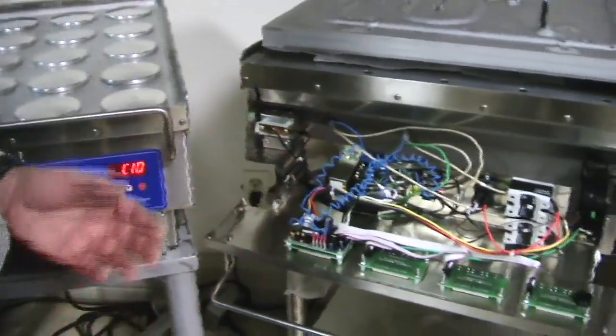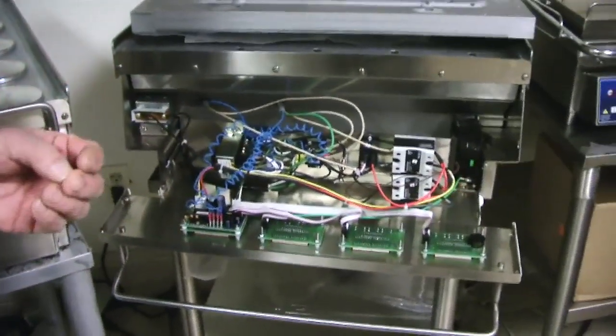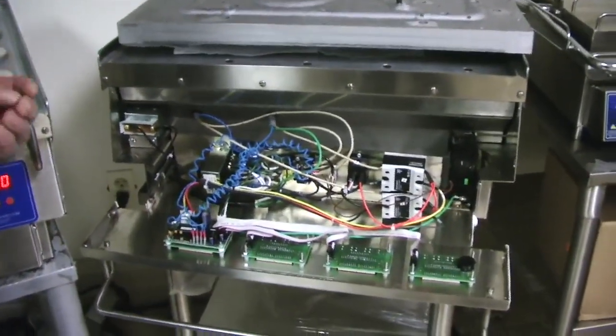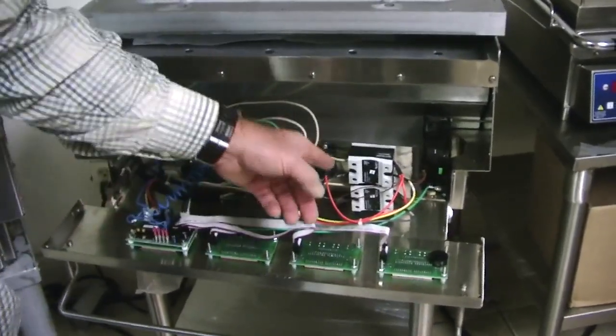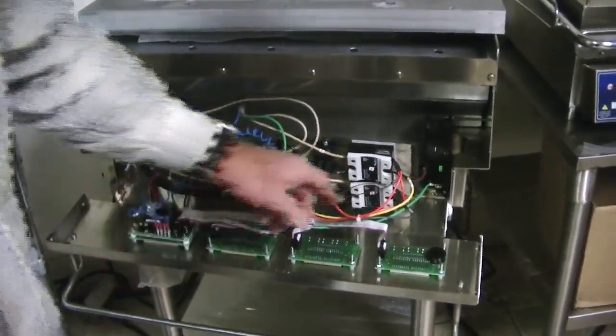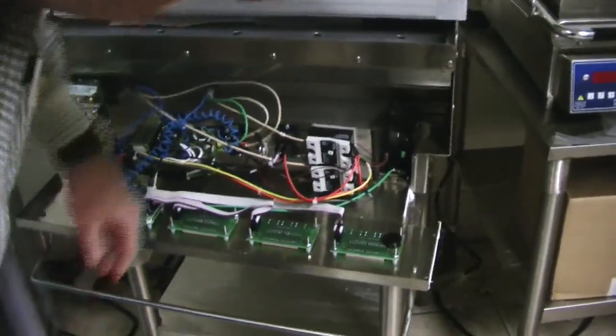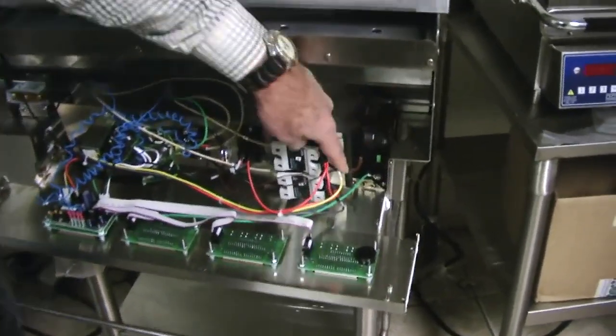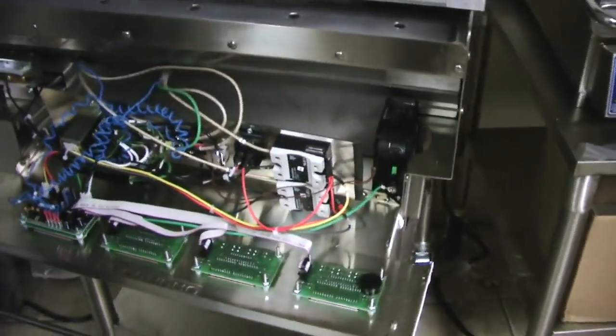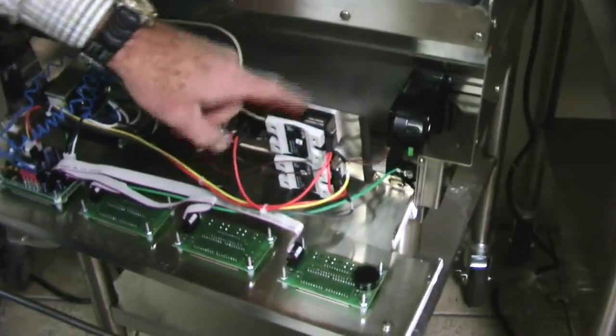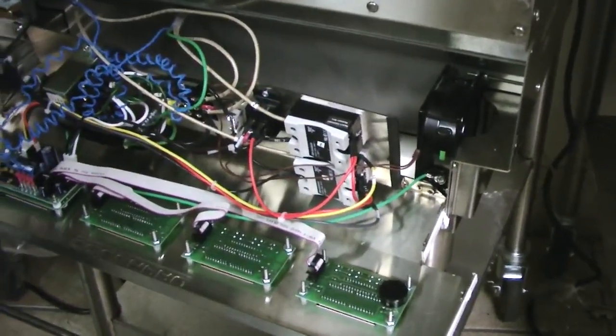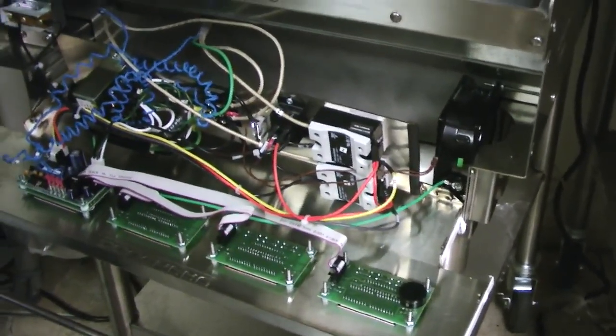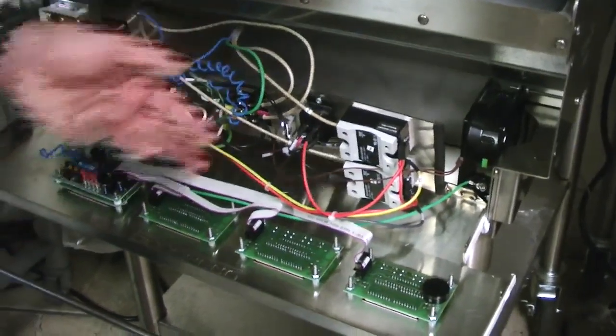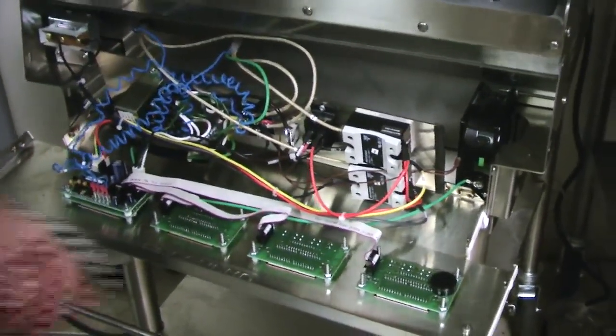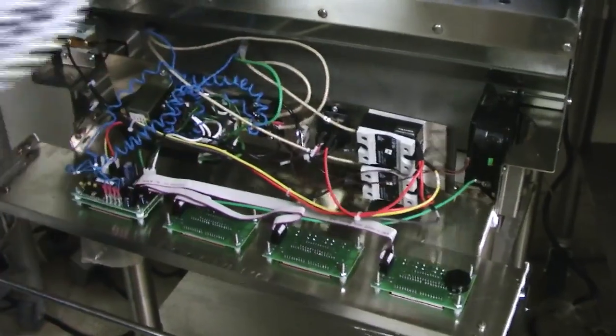The relays might have frozen in the closed position, and that I suspect with no signal coming to this relay from the controller, which is this side. If you're not getting 12 volts here, but yet it's still working and running, it's telling us that the relay is in the closed position, and runaway heat. Instantly replace the relay on it. And that applies for this one too.